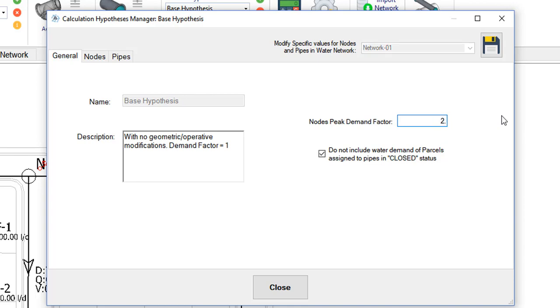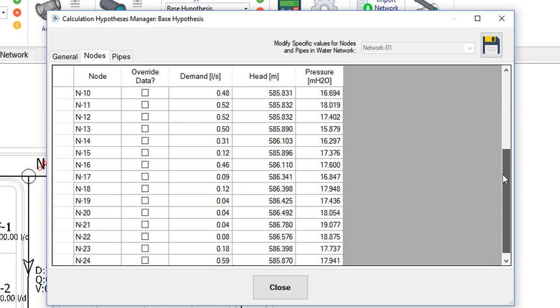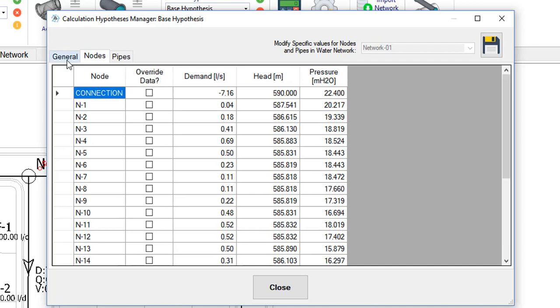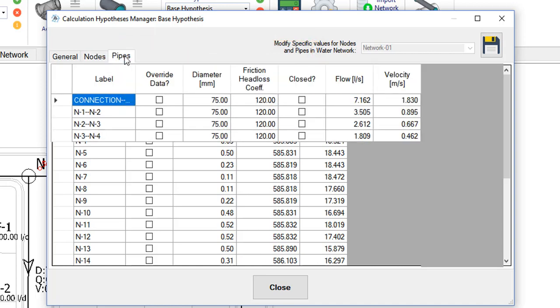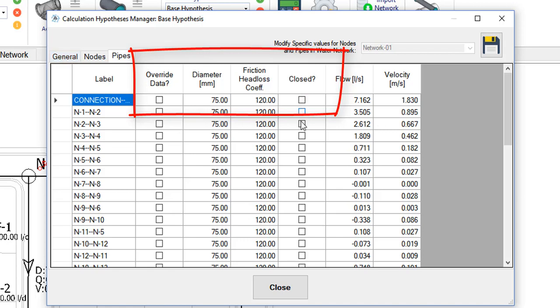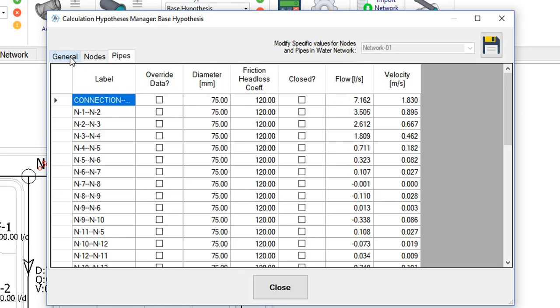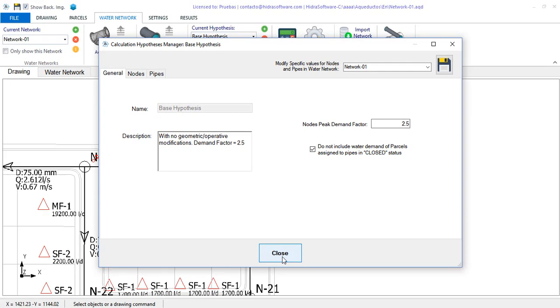In our case, 2.5 represents the maximum demand factor for this network's design. If we quickly review the nodes and pipes tab, we see that they contain the respective lists for the active network's objects in this project. Although in the base hypothesis no modification can be made, you will see that it is possible to create additional hypotheses in which you can modify parameters such as the demand or piezometric head of one or more nodes. For pipes, you can modify parameters such as diameter, friction coefficient, or its operational state, that is, set it as closed or open in the current hypothesis. We will see it in detail in other videos. Then, to modify the peak factor, I click the button save to store the changes and I close this dialog.